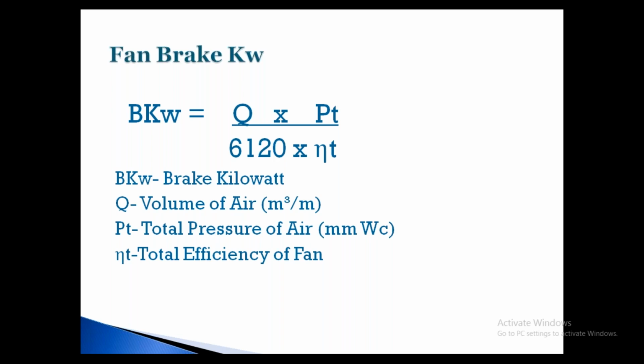So to know that, even energy audit or electrical or maintenance people, when you go for reducing the power in the plant, first we have to see what is the customer requirement of your RH, temperature, air balance, what is the total requirement. Then what type of fan they are using, if it is an existing plant. If it is a new plant, we have to explain to them about better efficient fan and best efficient fan. If you give that, the total running cost will come down. In such a way we should know what all the equipment involved is.